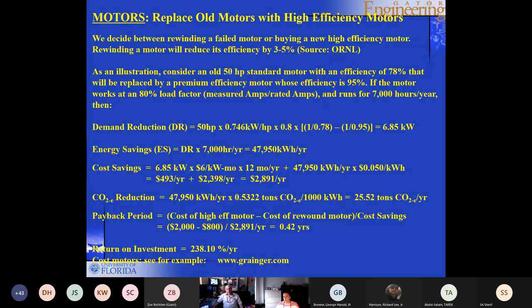And we're going to assume that it's going to run for 7,000 hours per year. So that's not quite the 8,760 hours per year. So 7,000 hours, you're going to shut these motors off a little bit. In this case, the demand reduction is 50 horsepower. You convert that into kilowatts by the multiplier, which is 0.746 kilowatt per horsepower. You multiply that by the load factor, the 80%. And then you multiply that by 1 over the efficiency of the old motor minus 1 over the efficiency of the new motor. And you're going to find that that produces 6.85 kilowatts of demand reduction.